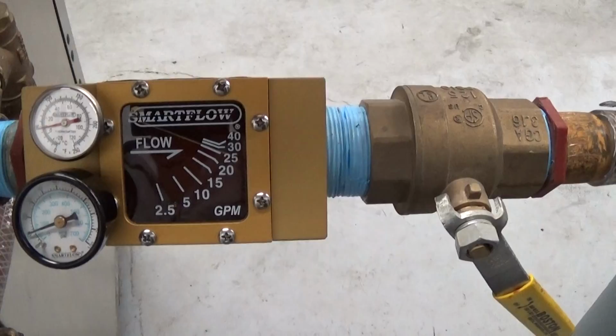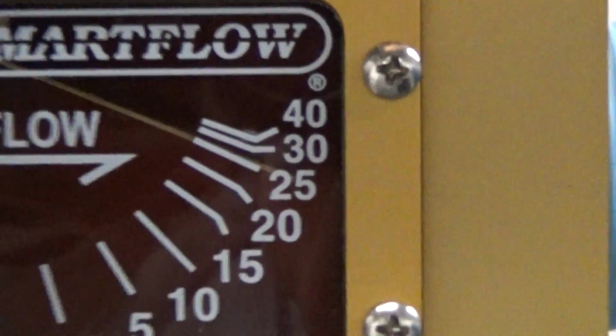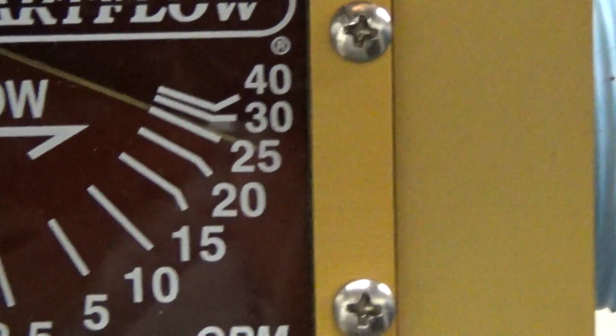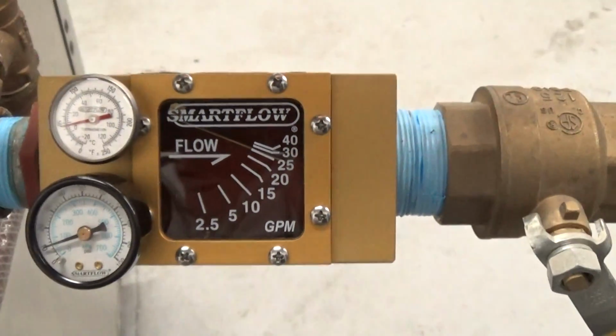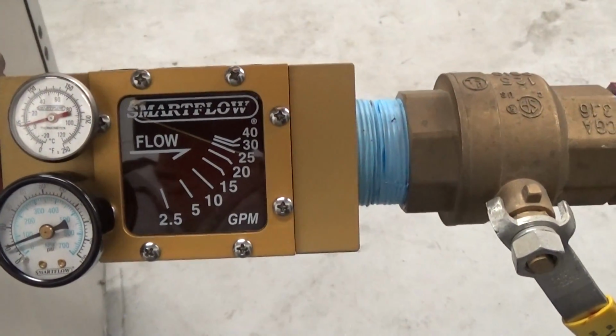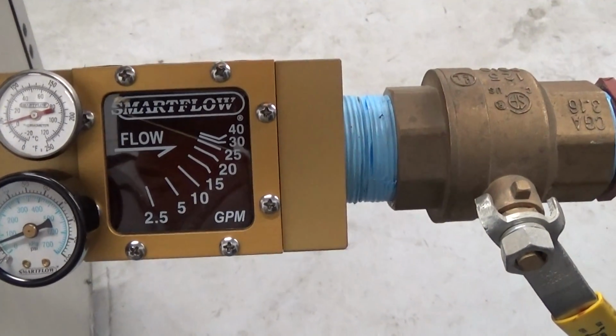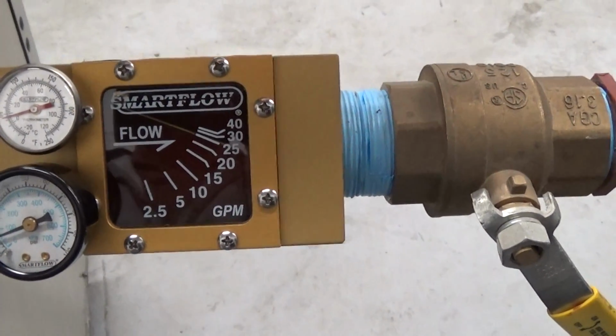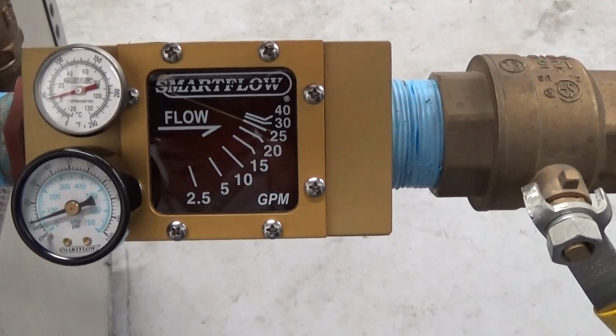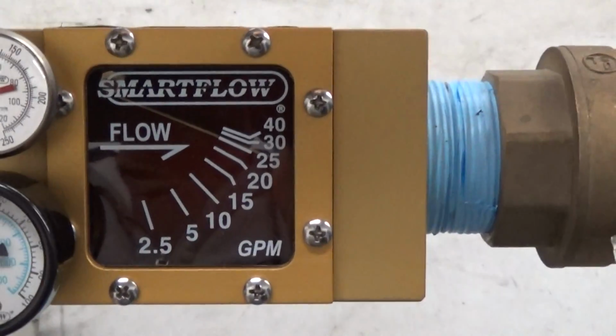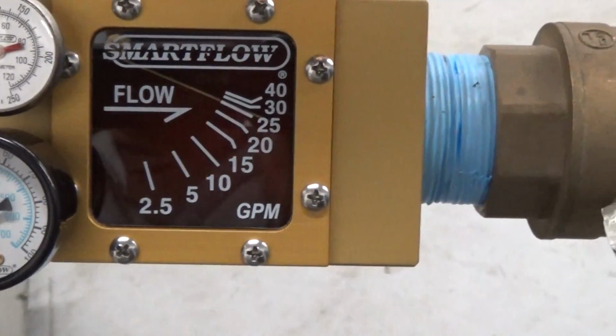We use a flow meter in all our testing. Right now, you can see we're at just shy of 30 GPM. As a general rule, about 2.5 GPM, 2.4 GPM per ton of cooling, this being a 10 ton or 10 horsepower. So we're right in the ballpark there.